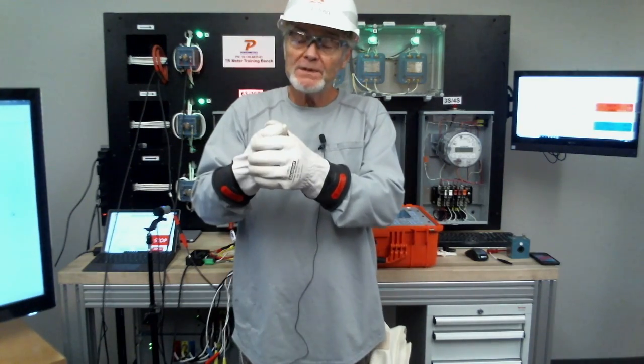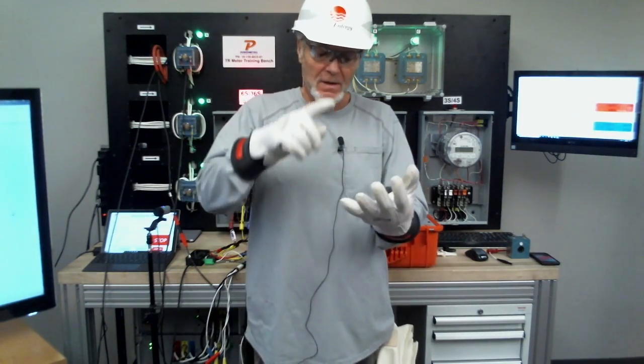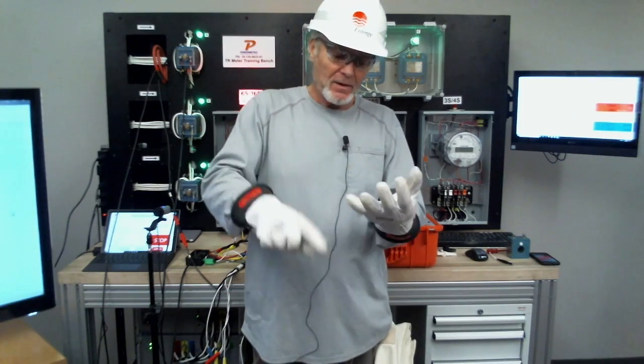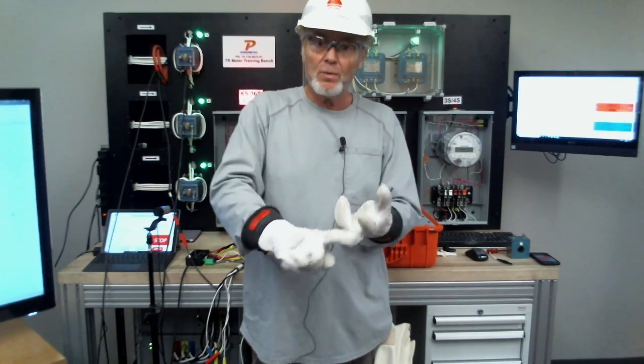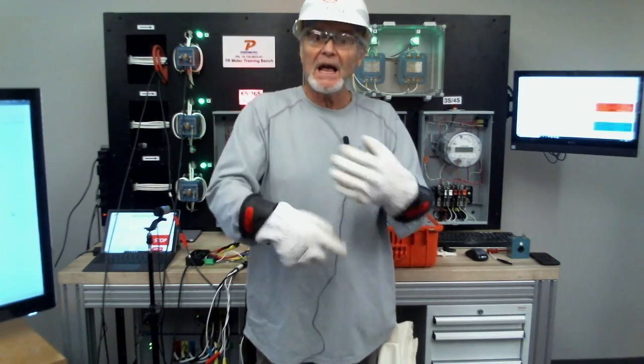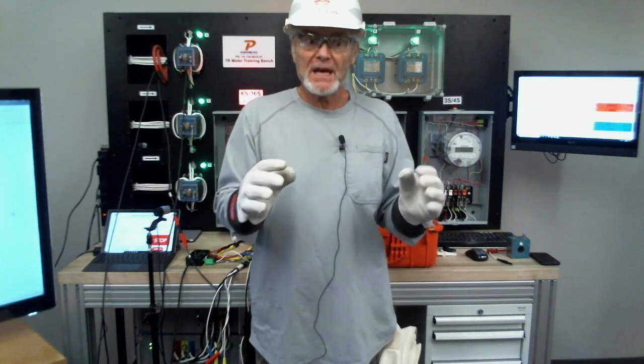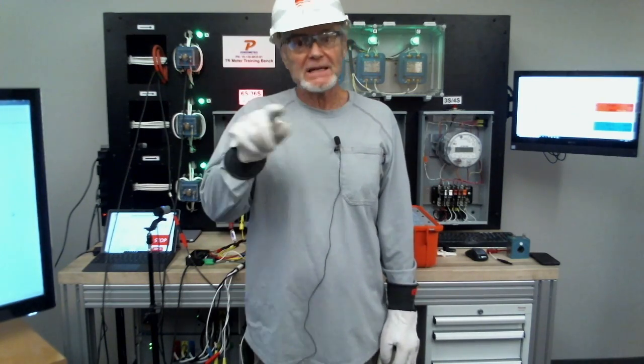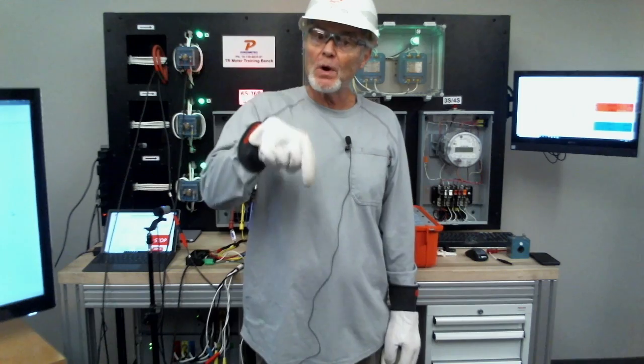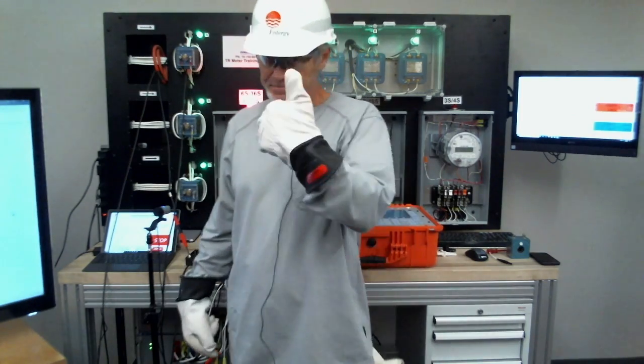If you leave it in probe set 2 and try to run that load boost, it's going to show polarity reversal, cross phase, low primary, low secondary errors, and sure enough when you go to run the test it'll show zero primary amps. It won't see the current because you've got to be in probe set 1, okay?